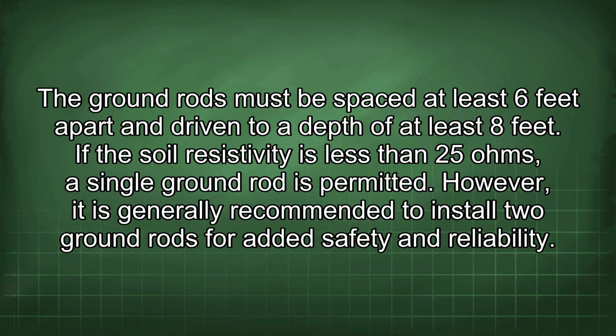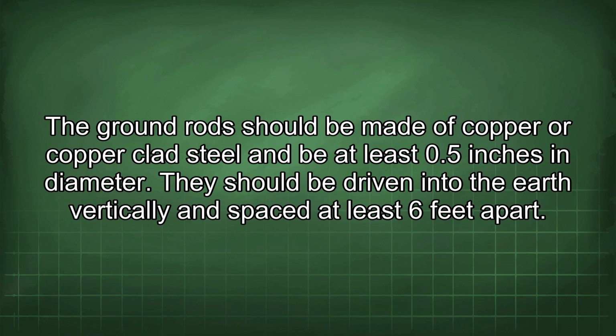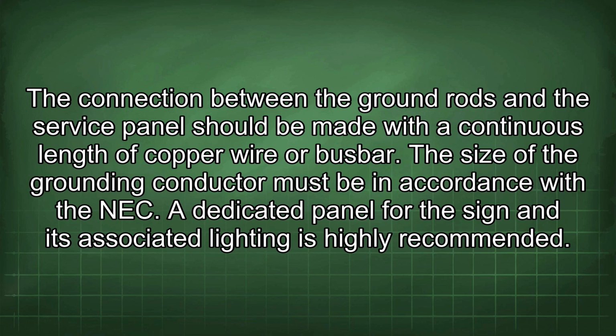However, it is generally recommended to install 2 ground rods for added safety and reliability. The ground rod should be made of copper or copper-clad steel and be at least 0.5 inches in diameter. They should be driven into the earth vertically and spaced at least 6 feet apart. The connection between the ground rods and the service panel should be made with a continuous length of copper wire or busbar. The size of the grounding conductor must be in accordance with the NEC.